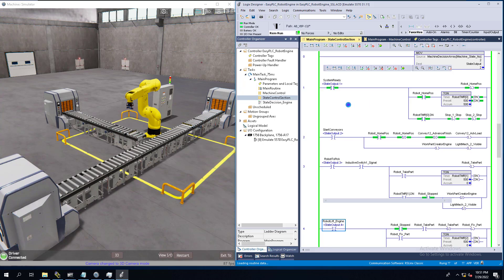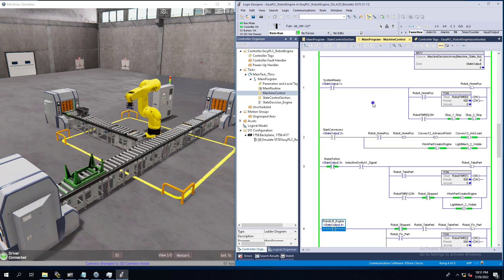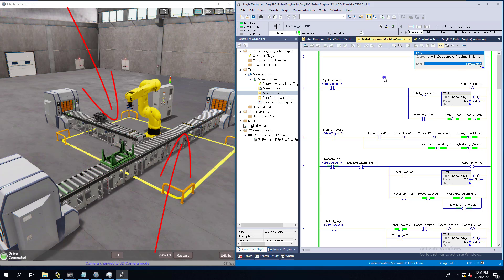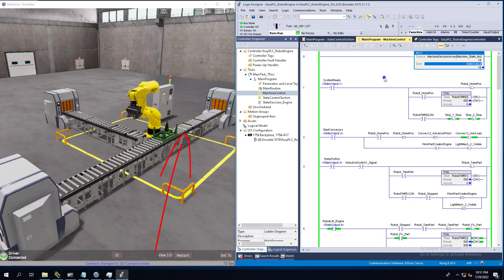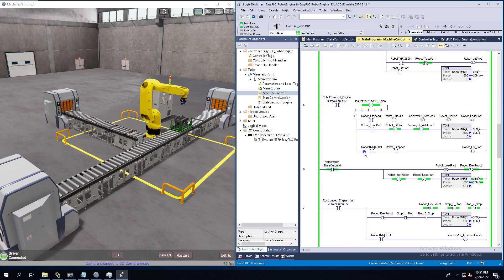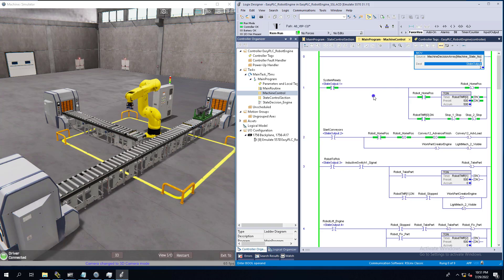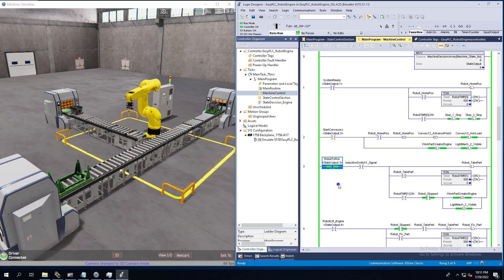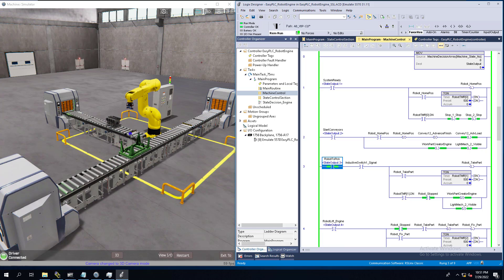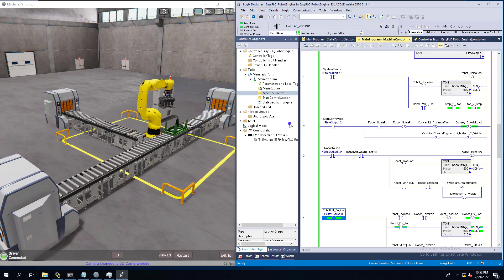Now that we know how it works, we're going to go ahead and hit the start button and see how everything runs. Watch the states go through — every time we change states it's going to change the value and change what's happening on the machine. You can see it's on at 16, which is bit 4. Now it's at 32 — you see them start stair-stepping their way through. Now we're back to bit 3, a decimal of 8, and it's looking for that inductive switch.